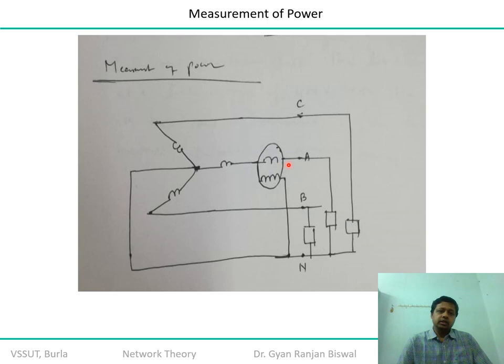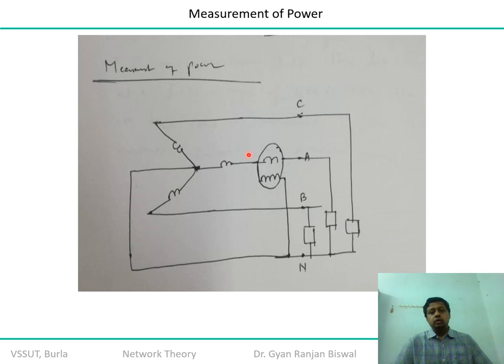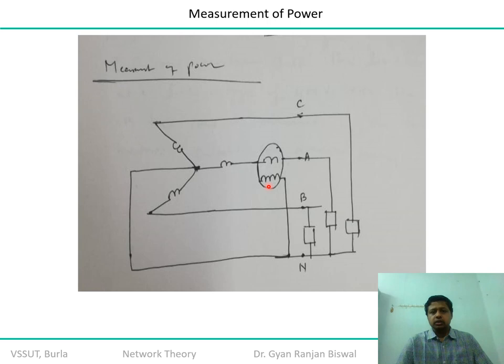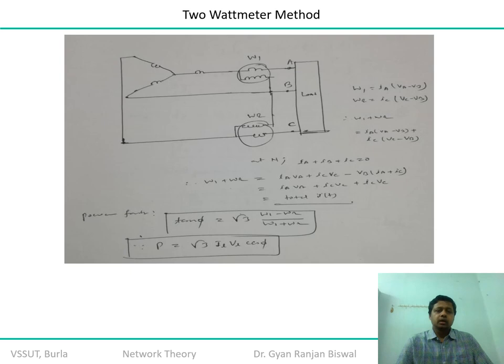The coil dedicated to measuring current should have fewer turns, because a higher number of turns generates more loss. The potential coil requires a larger number of turns to hold the required potential, and the current penetration through it will be less. The wattmeter is connected through a particular phase and to the load, so you get the real value of current and voltage, giving you the real value of power.